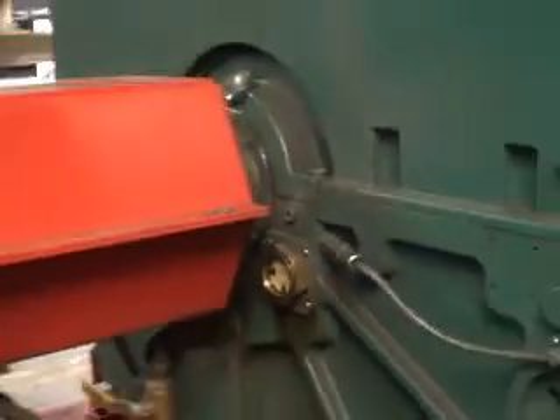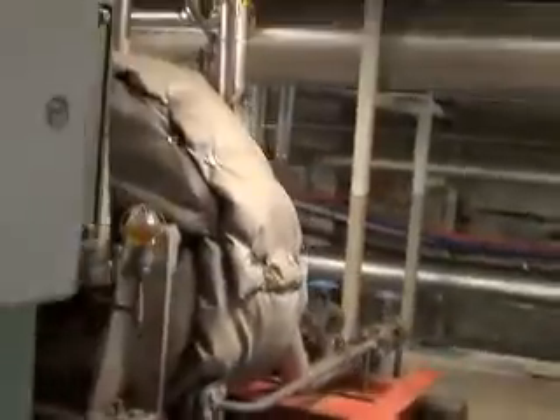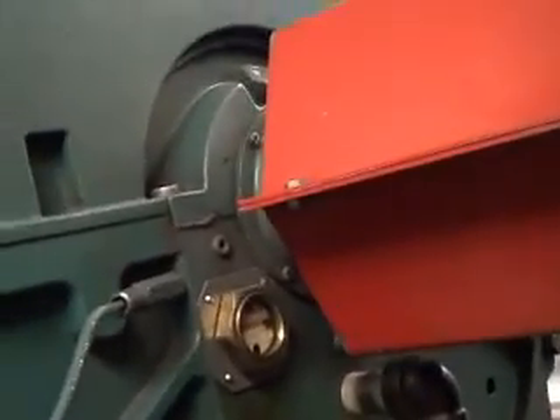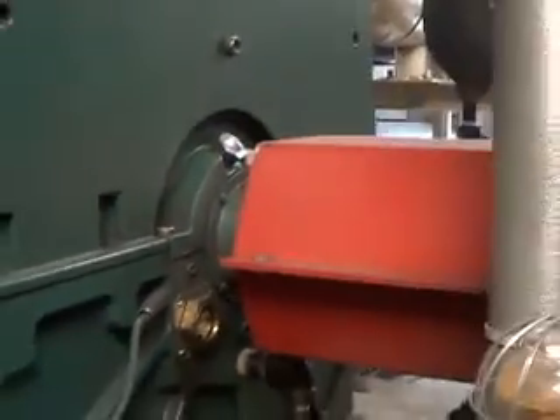You also want to check the oil level. That is some clean oil in the turbine bearings. Got that on both sides. This one is running at 145 degrees. 145. Oil level looks good.